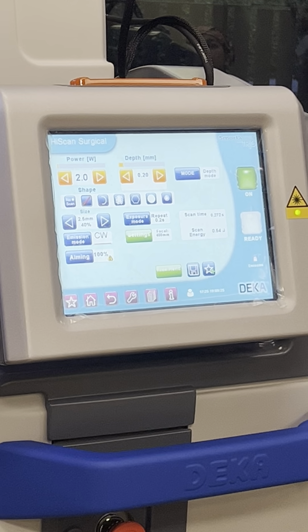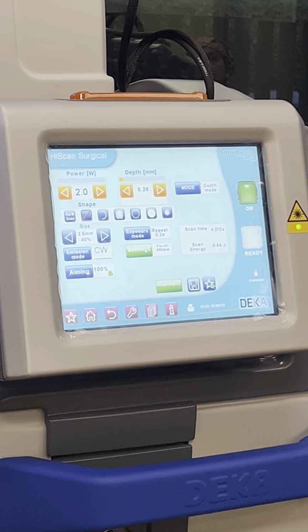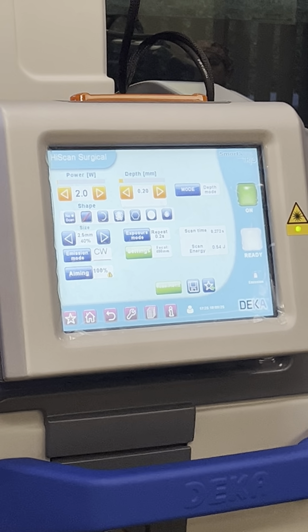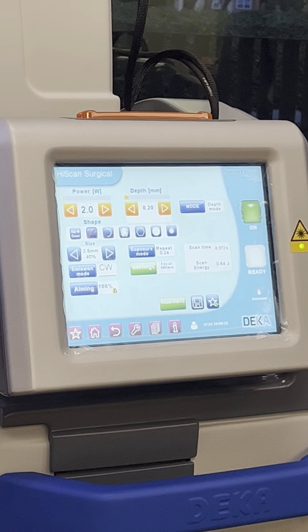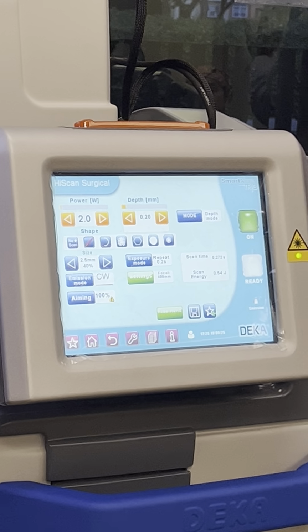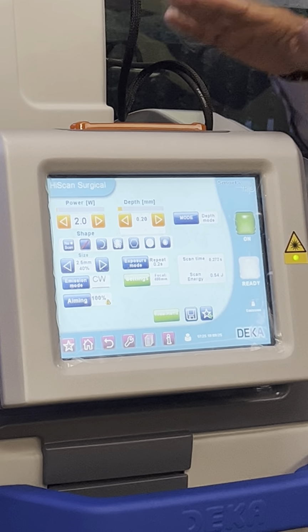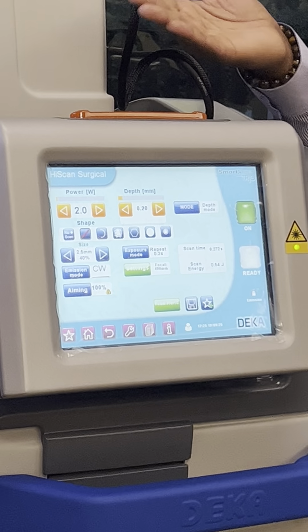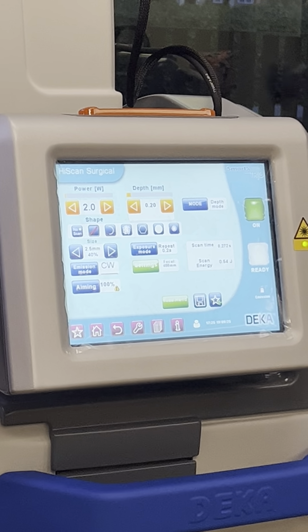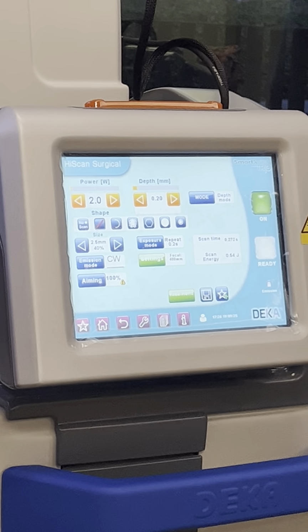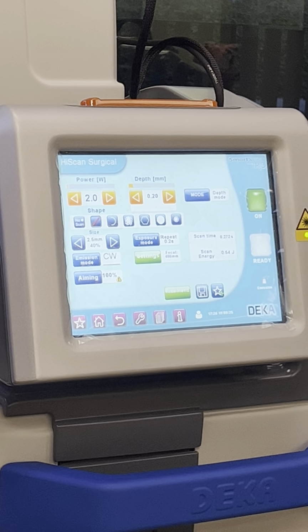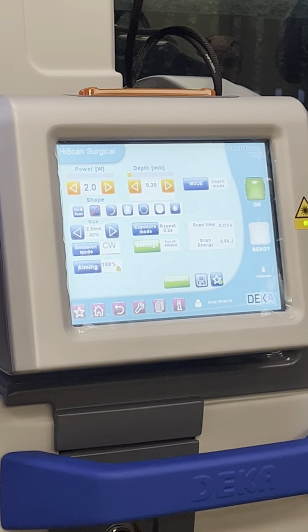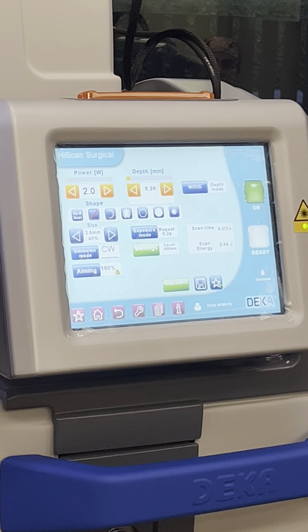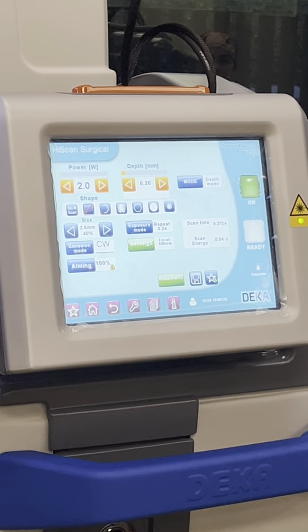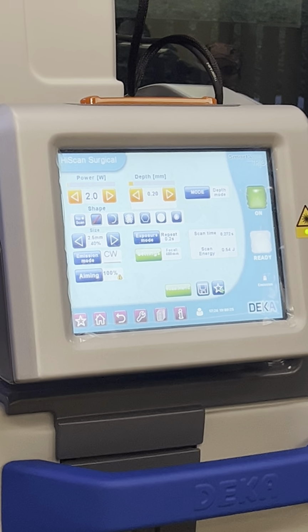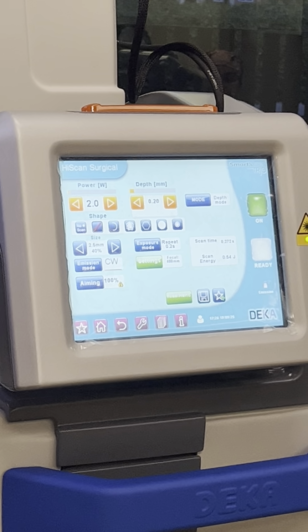Depth is how deep he wants the actual laser beam to fire into the tissue. Remember, you guys were using the Acupulse Duo. The doctor said, "Oh, I want a 1 for my depth, or I want a 2 for my depth." It's different on this machine because it's American standard versus metric. It's not exactly a 1-to-1 comparison, but a basic equivalent for a 1 is 0.2 millimeters. A 2 is about 0.4 millimeters, 3 is 0.6, 4 is 0.8, etc., etc.